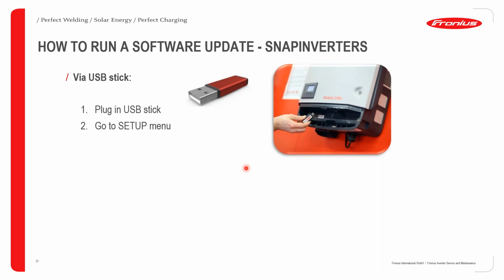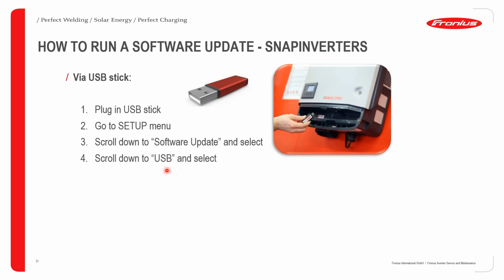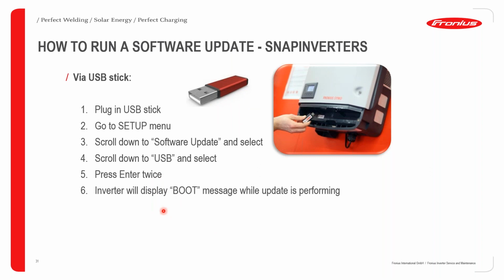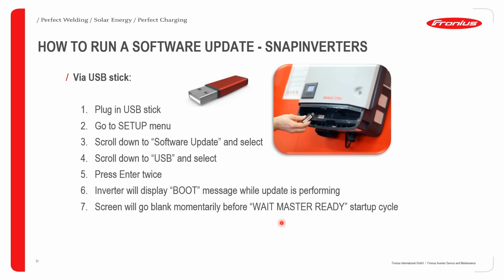Once you have your inverter powered up, go to the setup menu that you can navigate through the display of the inverter. Scroll down to the section that says using the buttons, software update, and select it. Then scroll down and select USB, because this is where you are going to be updating the software from. Tap the enter button twice, and your inverter will display a boot message while the update is performing. Once the update is complete, the inverter will go into a blank screen momentarily, and then the master ready or wait master ready startup cycle will display once again.